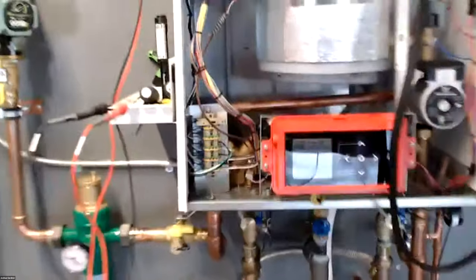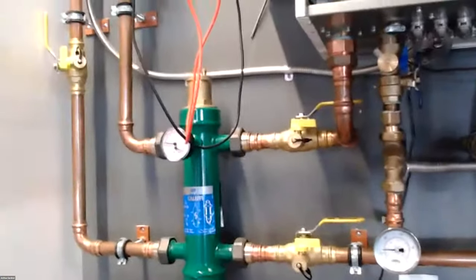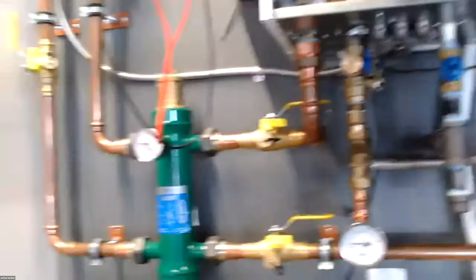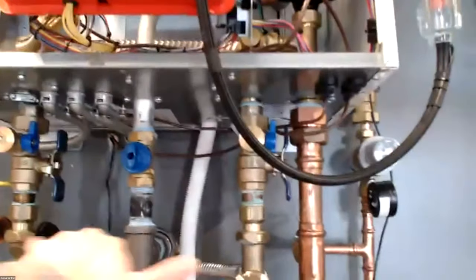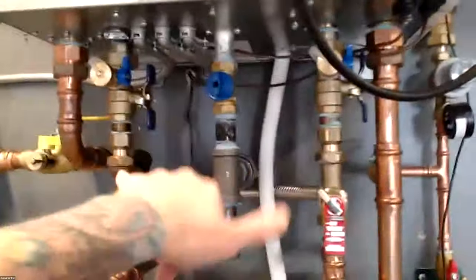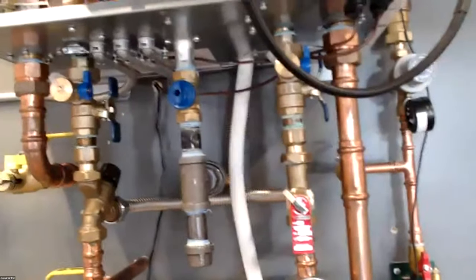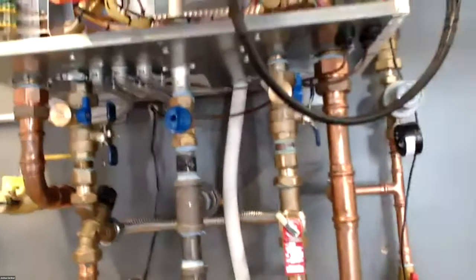So we have some piping installations here on a few of them. This one, Combi, this is really the best way to do it: get a low loss header, nice, clean, compact. We have that hydraulic separation. We have that air separation. Our domestic comes out, flush valve, mixing valve, not required, but definitely recommended. Pretty simple.